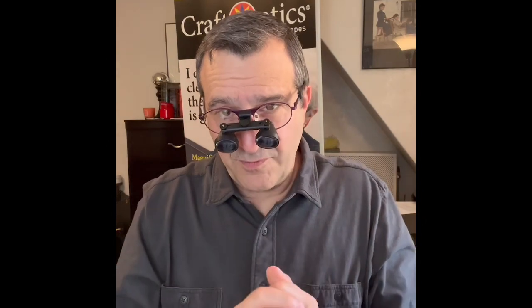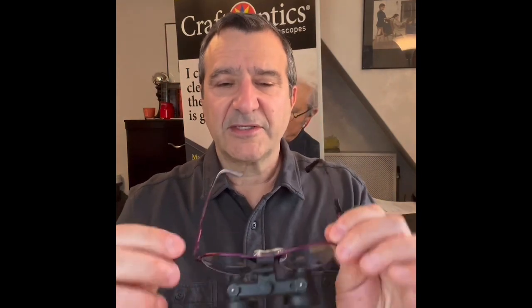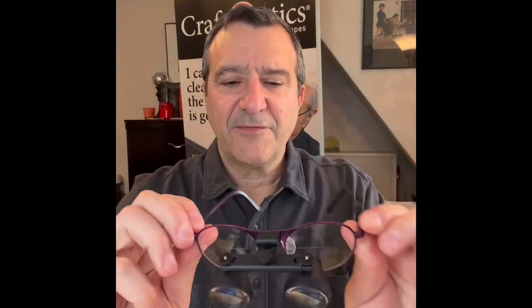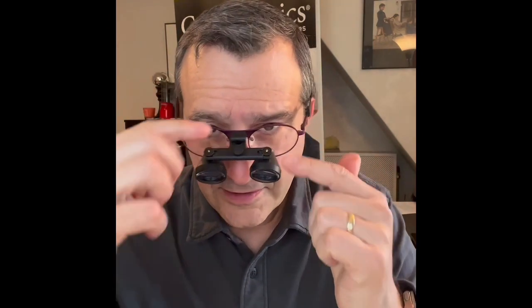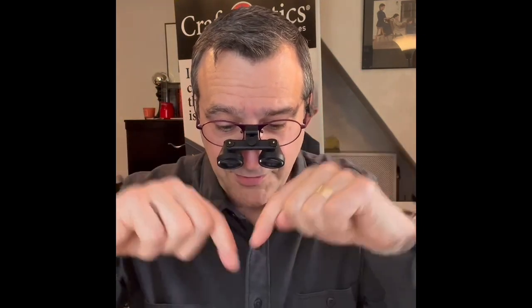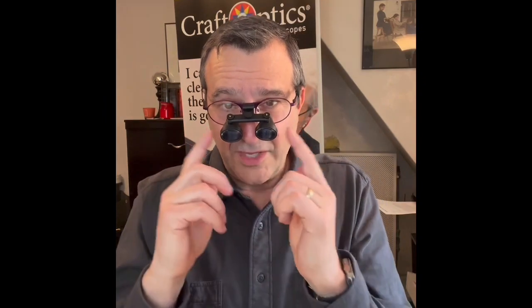If you have a narrow pupillary distance, I'm going to show you how to do that. For someone who has a very narrow pupillary distance, when you turn the knob you can only get so far — you can get to a certain point and then it stops. If you are narrower than the optics are normally designed for, you can actually adjust that by just squeezing these together like this, and you'll see how they are moving in closer. Obviously this isn't right for me — you can see my eyes are out here but the optics are here, so I would really have to almost cross my eyes to see through it. But if you have a narrower pupillary distance, that's how you make that happen. Always, again, look at something at the proper working distance while you're making that adjustment.